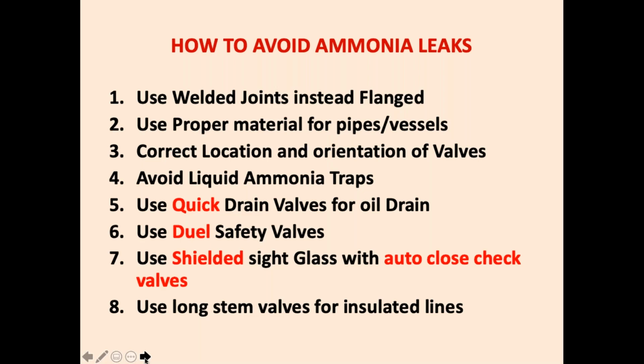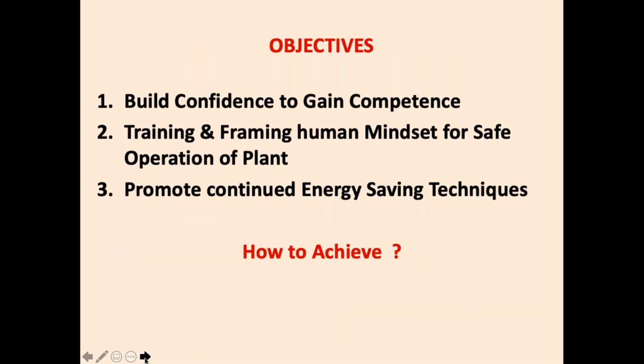Now, when we install a plant, the first biggest mistake we make is that valves are ordered in quantity: send 8 valves of 4 inch, send 6 valves of 2 inch. But you don't know where this valve is going in your plant. If it is an insulated line, if it is going on the suction line, then in 70-90% of plants I have seen that to reach the handle, people have to cut the insulation and only then is the handle visible. So long stem valves should be used for insulated lines. A very, very important point to be kept in mind.